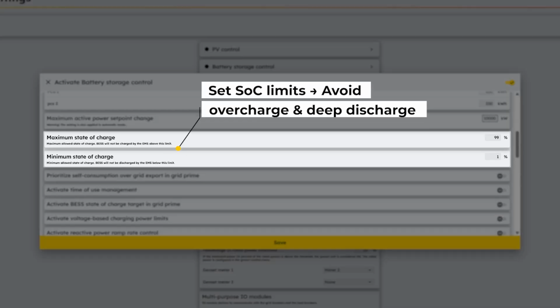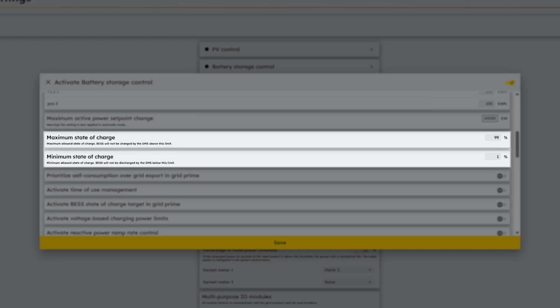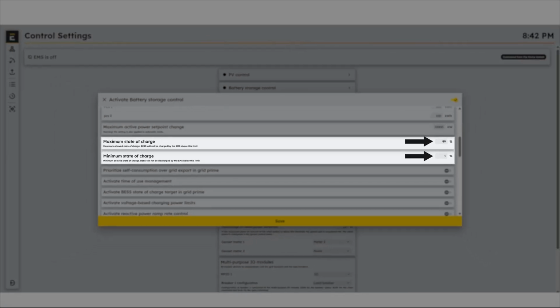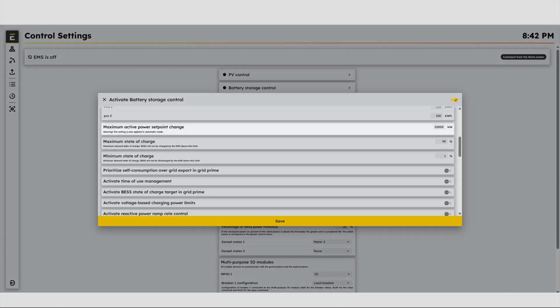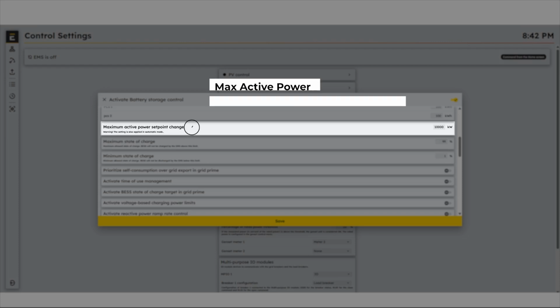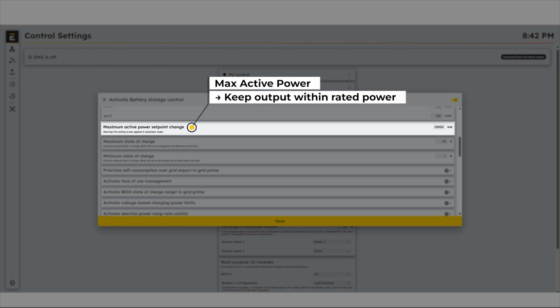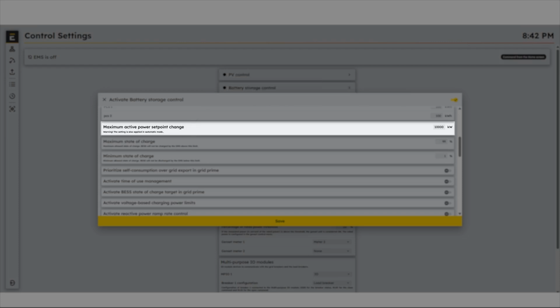Finally, the minimum and maximum SOC limits define the safe operating range of the batteries. The EMS will stop charging once the maximum SOC is reached and prevent discharging below the minimum value to protect battery health. The maximum active power set point change defines the ramp rate for the battery's active power. In other words, how fast the battery's power output can increase or decrease.